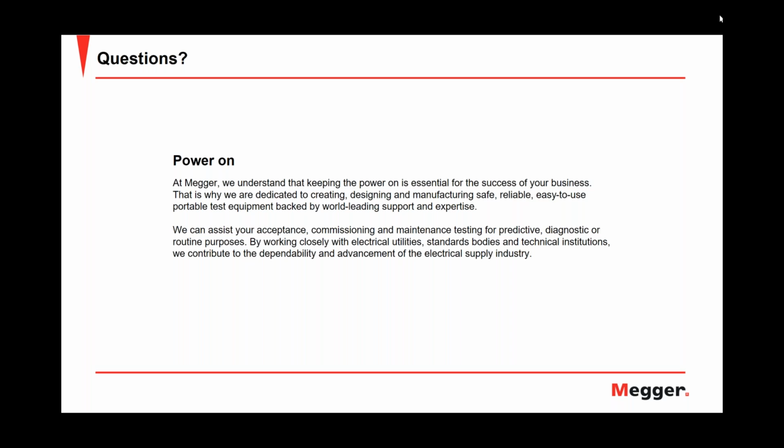And the other thing is simply, if you want to measure a phase-to-phase condition, you have to be connected phase-to-phase, say from A phase to B phase. But then keep in mind, Javier well explained the limitations there. The TDR can see very low impedance situations and very high impedance situations. One example was this burned-in-the-clear fault that Henning described, where the cable is pretty much destroyed at this point.